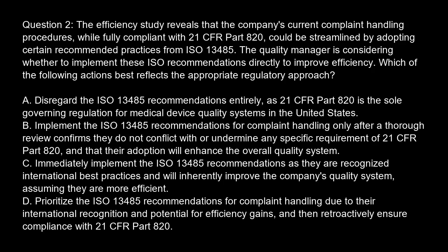Implement the ISO 13485 recommendations for complaint handling only after a thorough review confirms they do not conflict with or undermine any specific requirement of 21 CFR Part 820, and that their adoption will enhance the overall quality system.